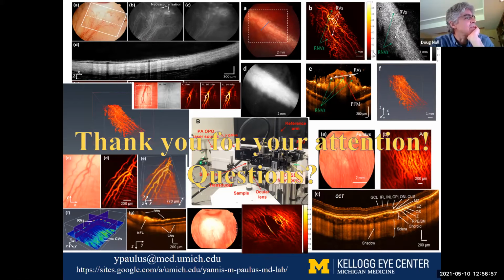Right. So Jim Weiland, is the acquisition time for photoacoustics similar to OCT? So you're going to be limited by whatever your light illumination source is. Right now we have a source that takes longer for the acquisition of the photoacoustic microscopy than the OCT, but that's really limited by our laser light source. So I would anticipate in a clinical system down the line having a much faster acquisition for photoacoustic microscopy that could just take a couple of seconds.